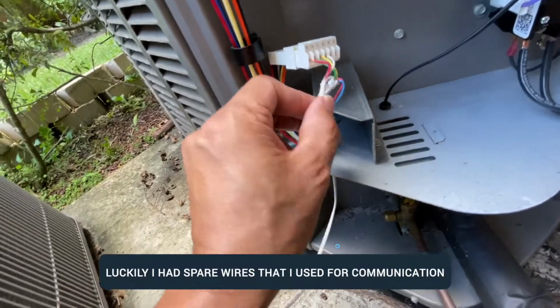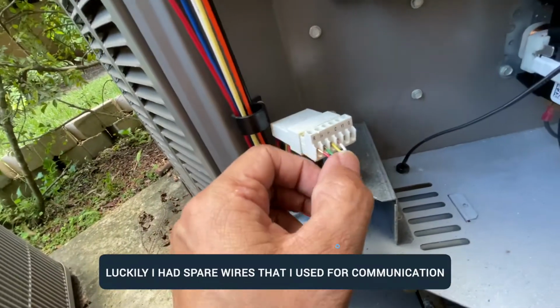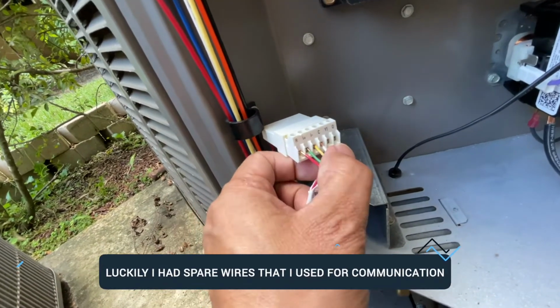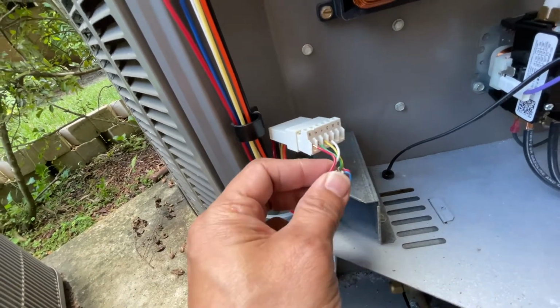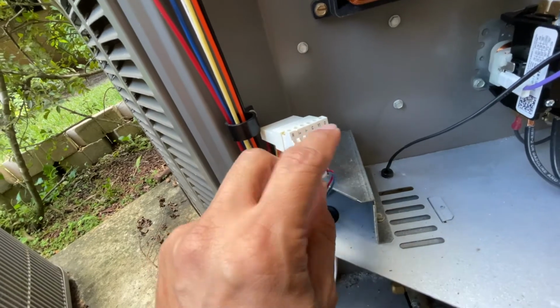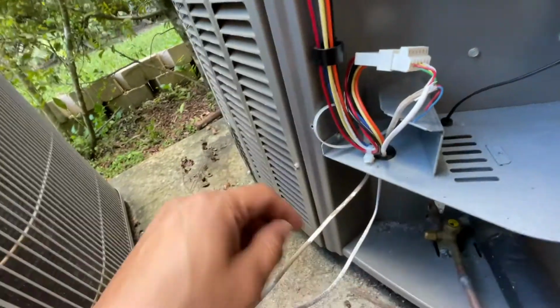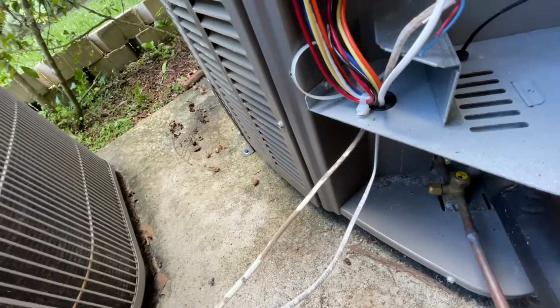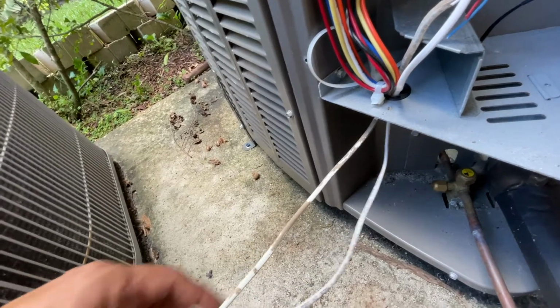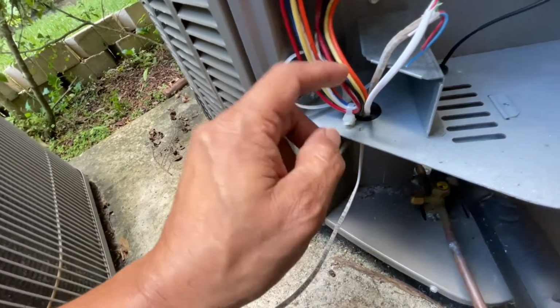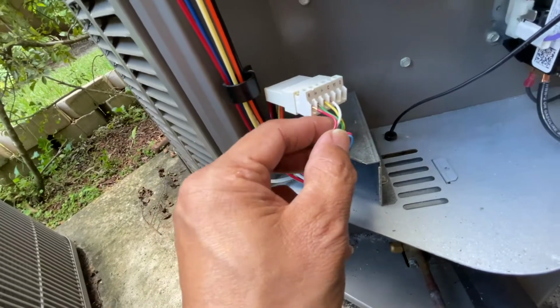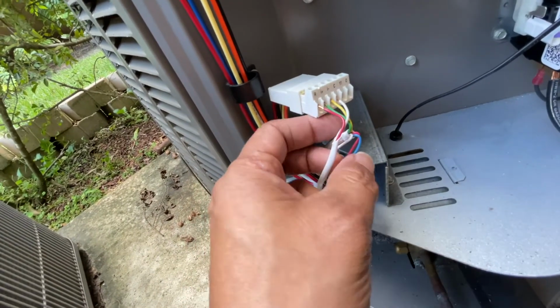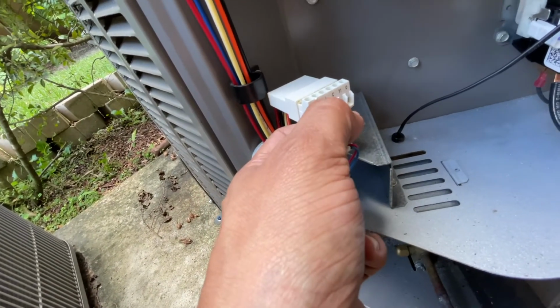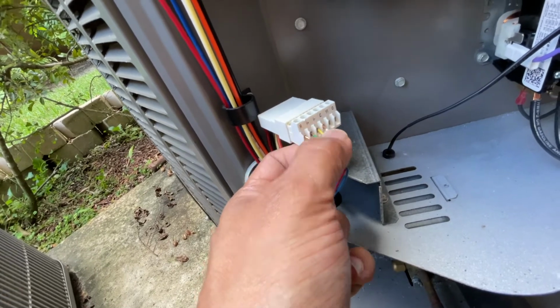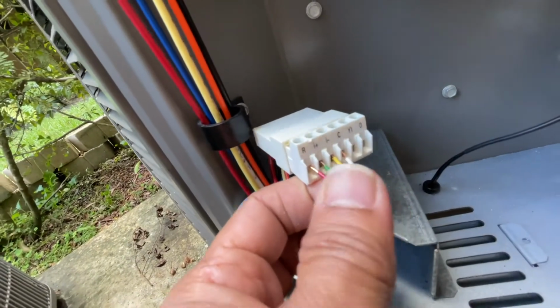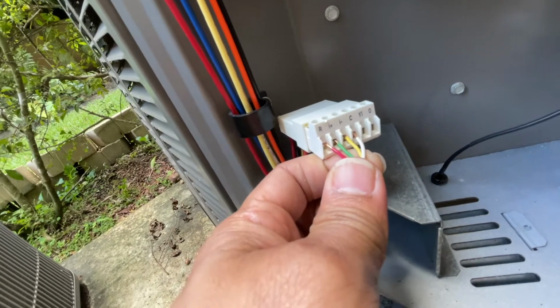So this one comes in as red on red, C for common. These are coming from upstairs, matching R and C. And for the communication, this is the spare one that wasn't being used. I'm using this one now for the spare, and this one for communication. There's going to be the yellow for I minus. Right here you can see yellow for I minus and green for I plus.